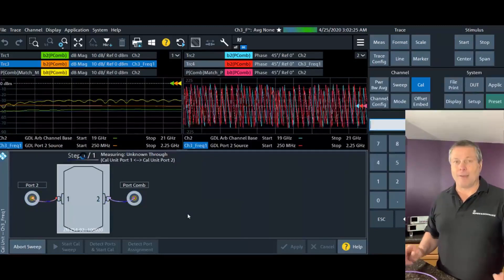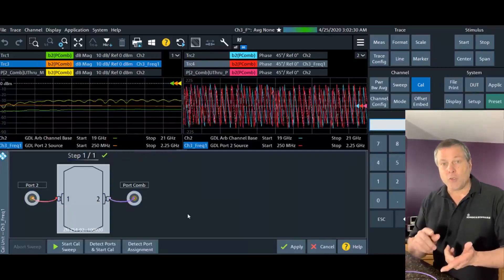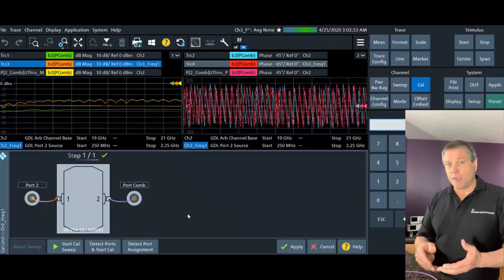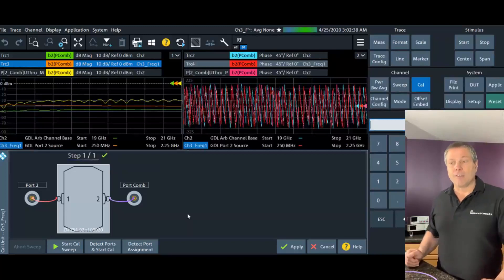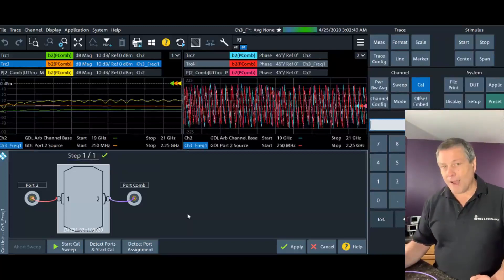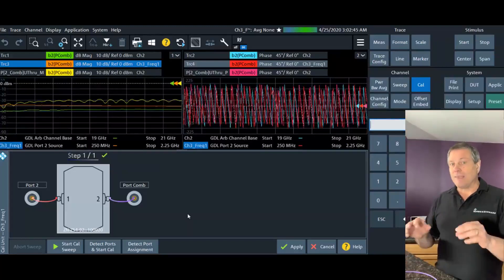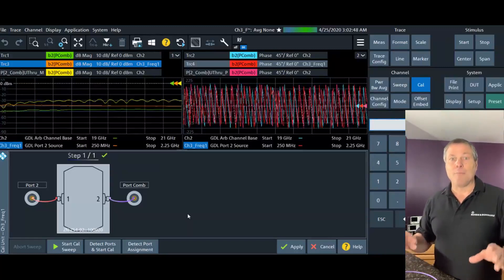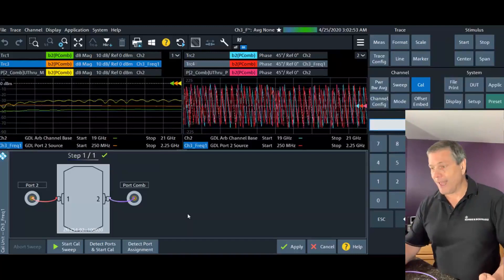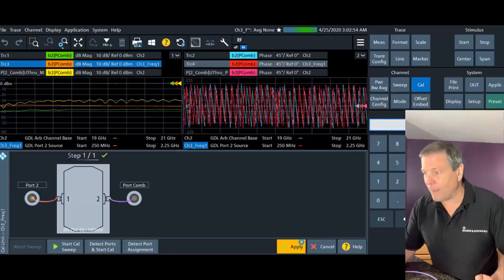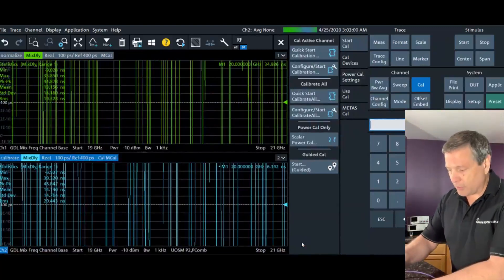I'm still using 6 dB attenuators on my port 2 cable to settle down the mismatch that occurs between the device under test and the VNA. Even though I'm going to be applying an error model, I still want to take advantage of the attenuator for mismatch correction. To me, this error model doesn't mean stop using attenuators — it means let's reassess how good we can make our measurement and go even further. So let's apply this calibration, and in the second step I have to redo the mixer delay calibration.